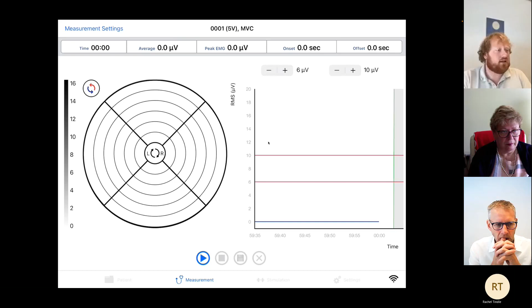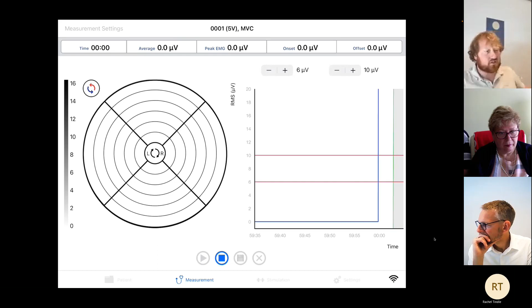At the bottom, we have the start and stop buttons, the save buttons, and the back button. So if I press the start button and my patient is connected correctly, just do that here, like so. I press the start button, and it takes a second because the system first does a number of safety checks. It sets the zero potential of the body with the reference electrode. It does the primary measurement with all active electrodes, and then it sets the average EMG signal between all electrodes, and that's what you see in the line graph.